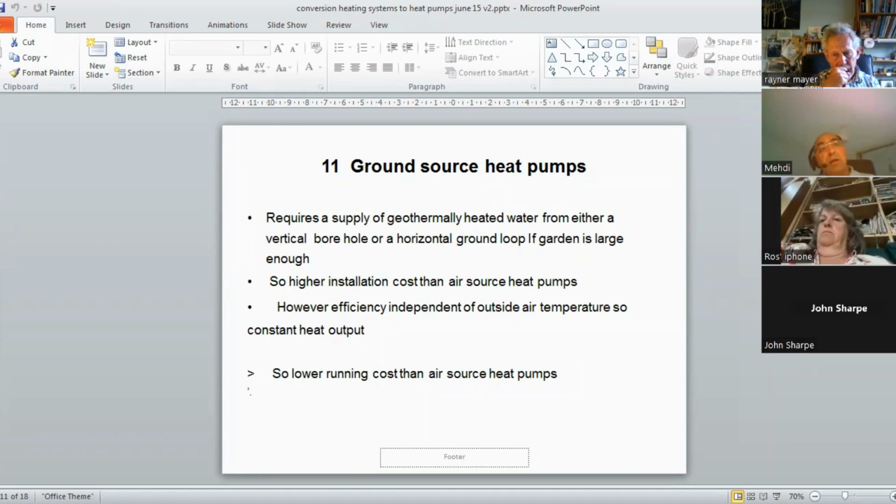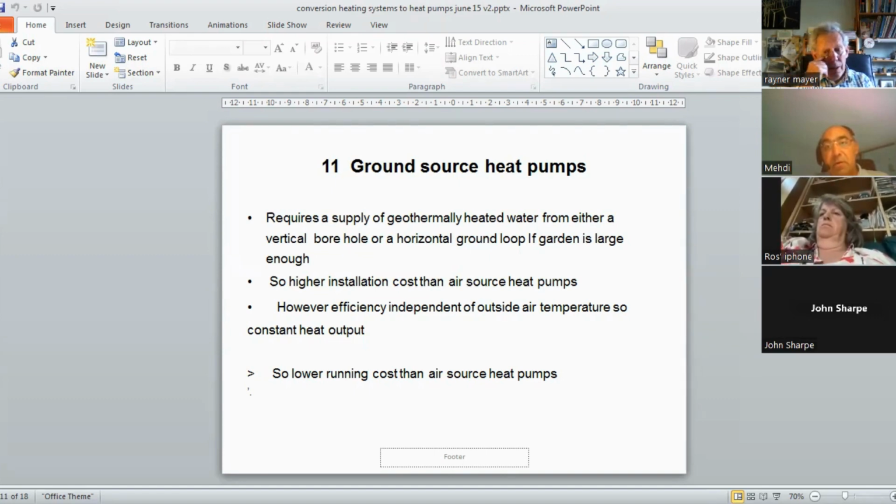One point that I just wanted to highlight is that it's not applied to domestic buildings, but there are many commercial buildings in London, I'm aware of 3 of them, where they put the boreholes on the ground and build the building on top of the boreholes. That can be structurally okay, but let's assume it happened for 2 of those 3 that there was a need for maintenance of those ground heat exchangers, and at the end they decided to put a cap on them and find another solution. We always need to think about the means of maintenance for those ground heat exchangers. Otherwise, in the long term, we have to forget about those ground heat exchangers without maintenance.